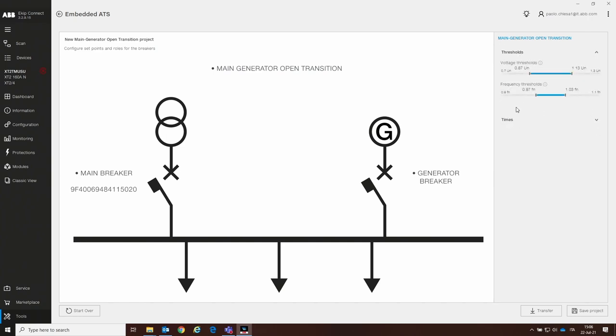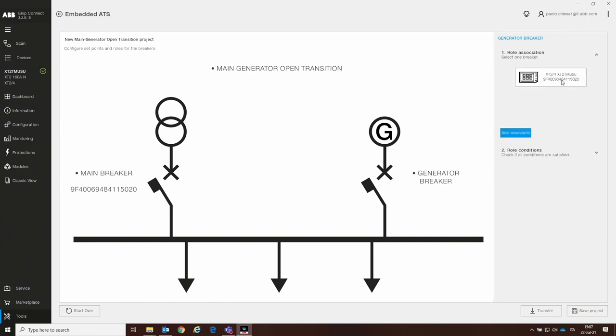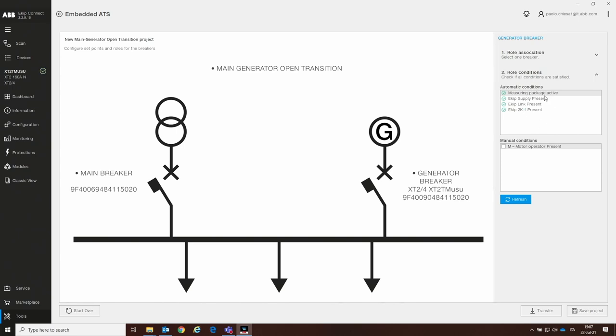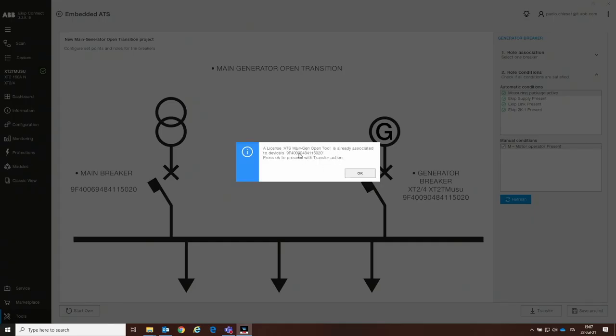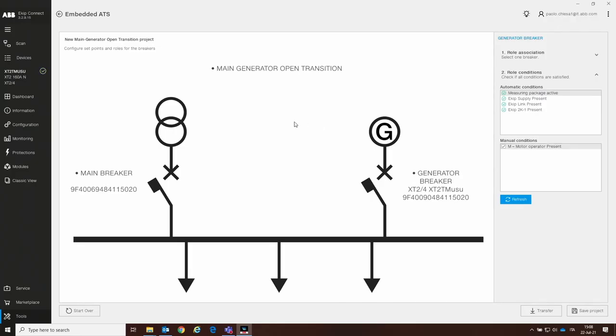My main-generator open transition settings are stored as I configured before. Now I click on the generator breaker, click on the role association button, select this new trip unit I'm connected to, and perform the role conditions check again. In this case all required items are present — I just need to flag the motor operator and then click Transfer again. The warning pop-up appears and I click Yes. Since a license was already associated, I click OK to override the settings with the new automatic transfer switch configuration. The transfer is completed — generator breaker transfer success. Main breaker transfer failed, of course, because I'm not connected to that one. My solution is now downloaded on both devices.